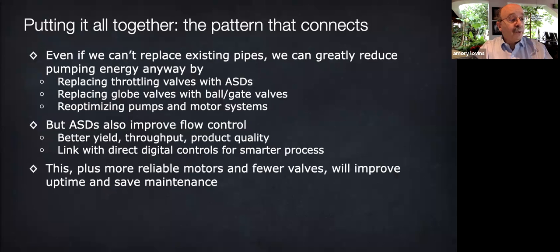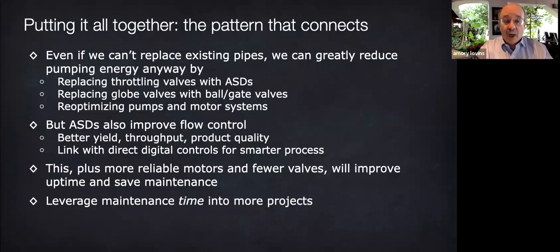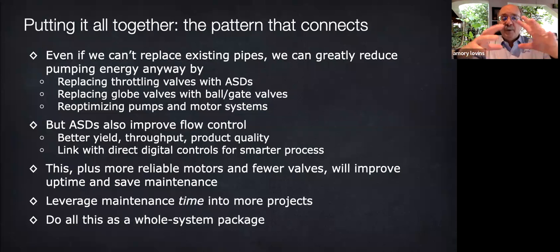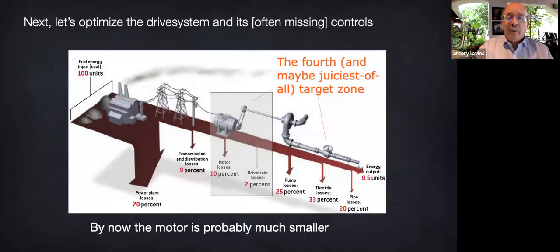Now, these changes will also tend to improve reliability, and that can also free up maintenance budget and time to leverage savings elsewhere in the plant. So your system boundary needs to keep expanding from the pumping system to the whole process, to the whole factory, to the whole company and beyond. Once you've minimized required flow, pipe friction, throttling losses, which should be zero because you run the pump at variable speed, and pump losses, your much smaller and more efficient pump will probably need a much smaller motor and control, usually an ASD, to provide the needed torque to run the pump.